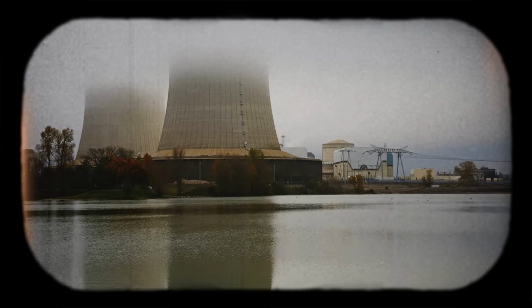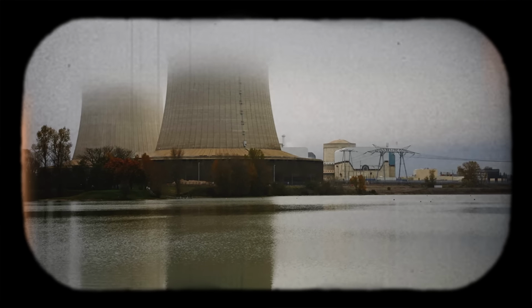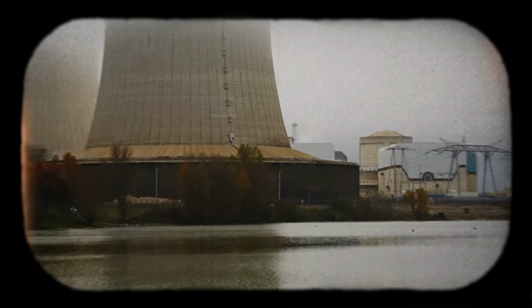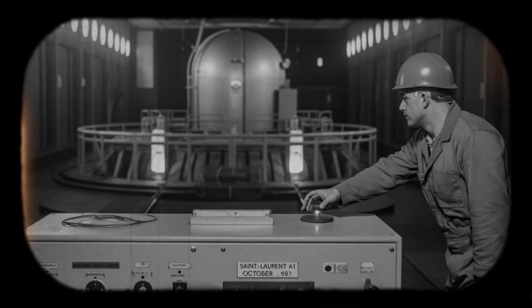Cladding temperature begins to rise. Magnesium-zirconium alloy, chosen for its neutron transparency and corrosion resistance in carbon dioxide, has well-defined temperature limits. Below 600 degrees Celsius, the alloy maintains structural integrity. Above 700 degrees, it softens. Above 800 degrees, it deforms and begins to melt. The fuel inside, natural uranium metal, has a melting point near 1100 degrees Celsius.